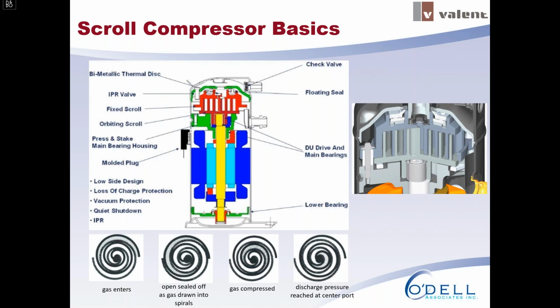in action. So you'll see the bottom scroll is rotating, and the refrigerant enters the scroll, and with that rotating motion, it's compressed until it reaches the very center, and then it's discharged. And then that cycle repeats continuously as it operates. The blue section of the top scroll, you'll see it just moves up and down once in a while, and that's showing the unloading of the compressor. And that's how a digital scroll modulates its capacity.